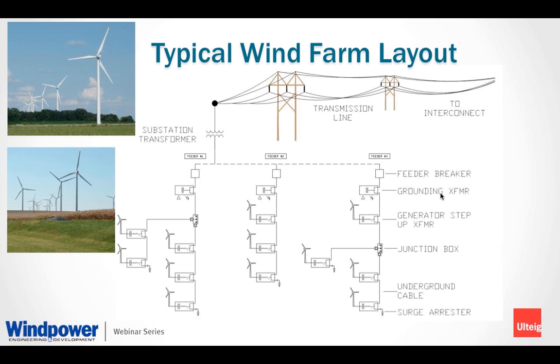So starting from the top, the transmission lines that are connected from the grid go down to a substation transformer. And this substation transformer generally steps up your voltage from 34.5 kV to 69 kV to approximately 345 kV. The extreme high voltages help with energy losses through the transmission line. That's also one area you can look at your conductor, as these transmission lines flow miles and miles to get to where they need to go in order to distribute power to everyone.